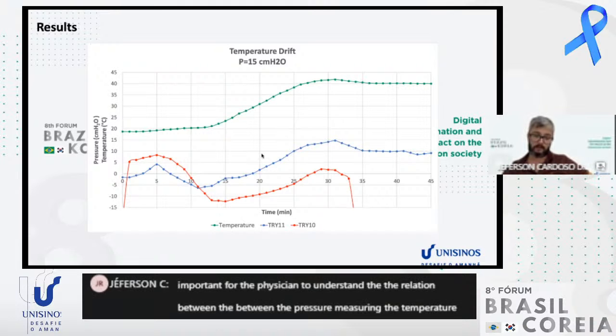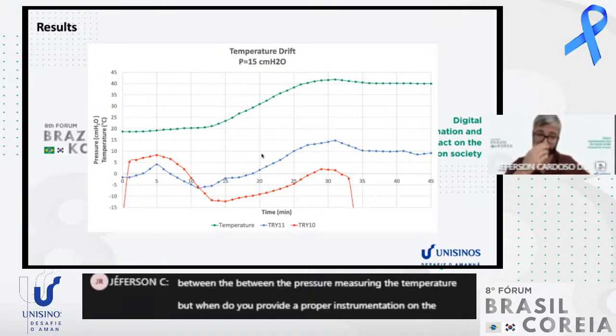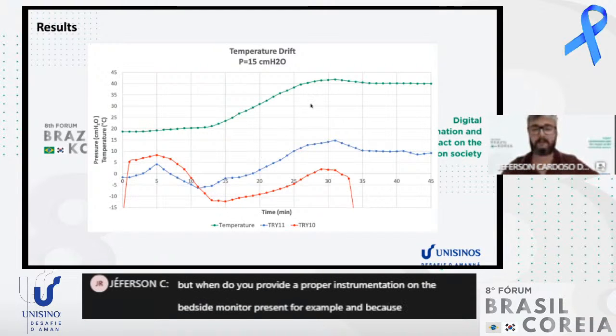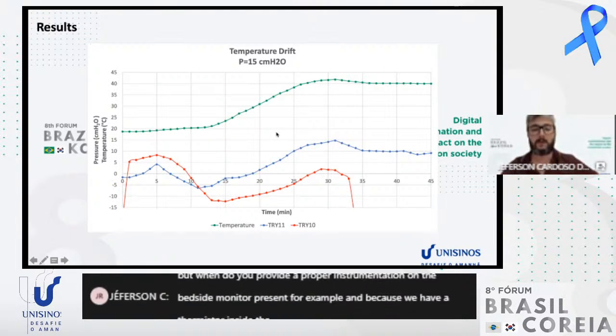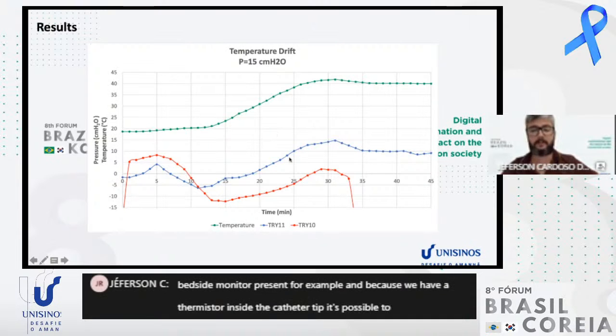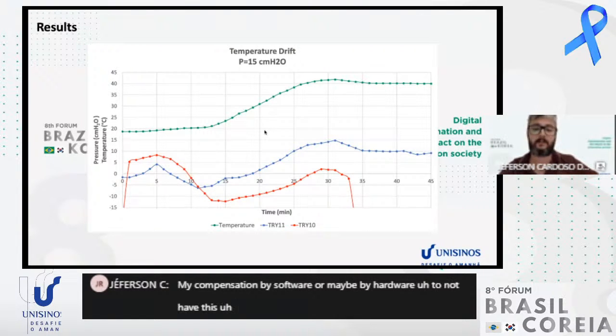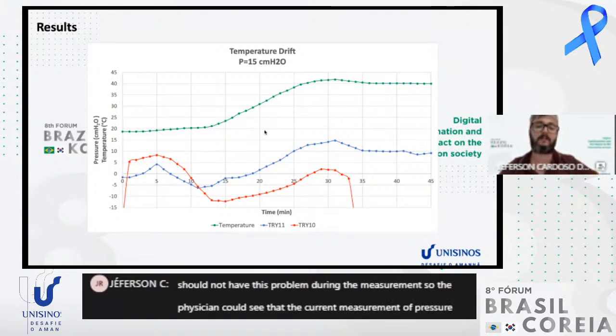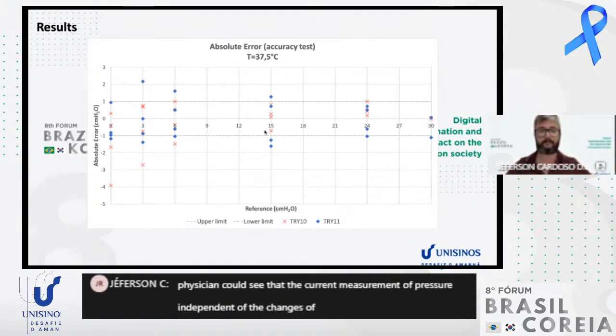But when you provide proper instrumentation on the bedside monitor, for example, and because we have a thermistor inside the catheter tip, it's possible to measure that temperature and apply a compensation by software or maybe by hardware to avoid this problem during the measurement. So the physician could see the correct pressure measurement independent of the changes in temperature.